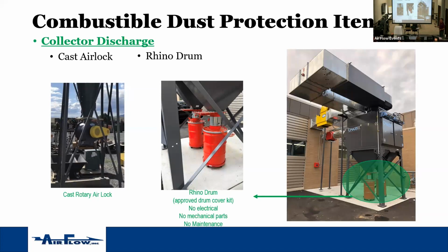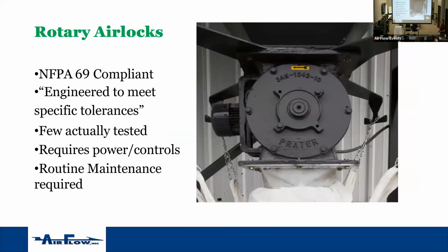And again, Rhino Drum is only good up to a certain KST. They only test it up to, I think, a 185 or a 190 KST. Once you get above that, it's going to throw you into a device like a cast rotary airlock. Their NFPA, cast rotary airlocks have to be NFPA compliant.